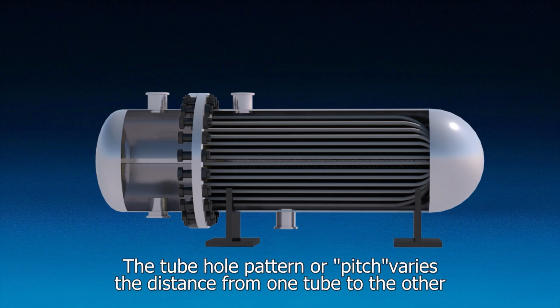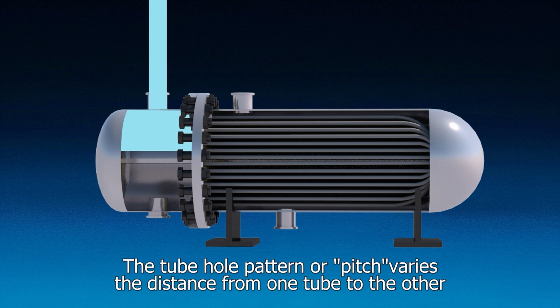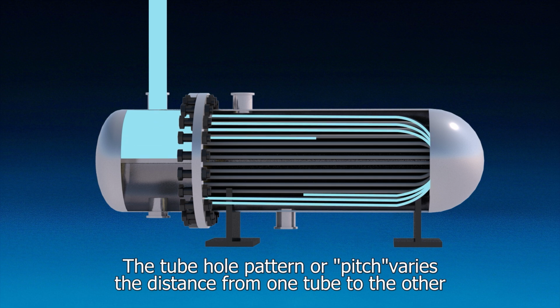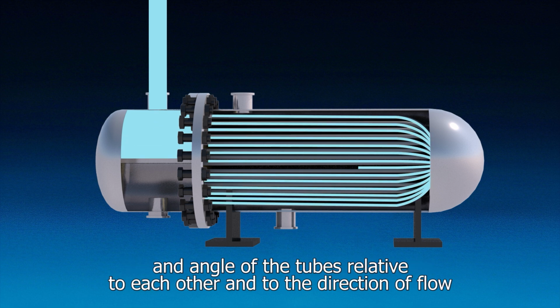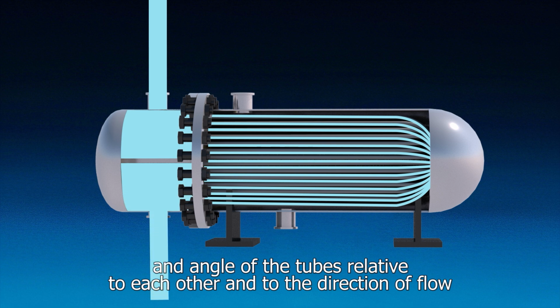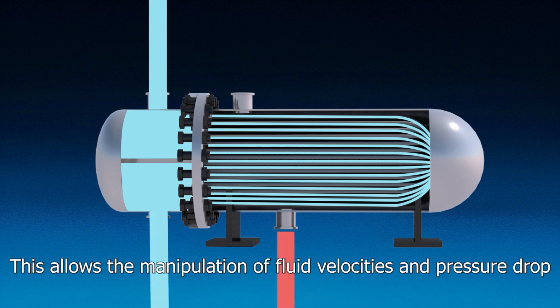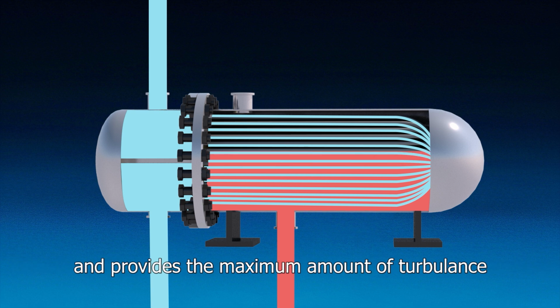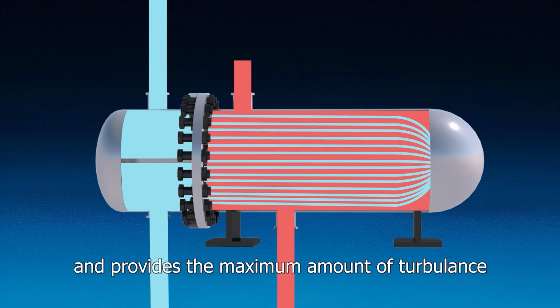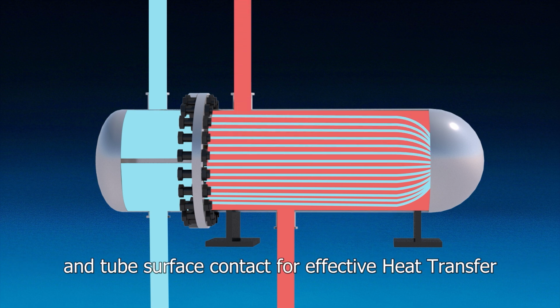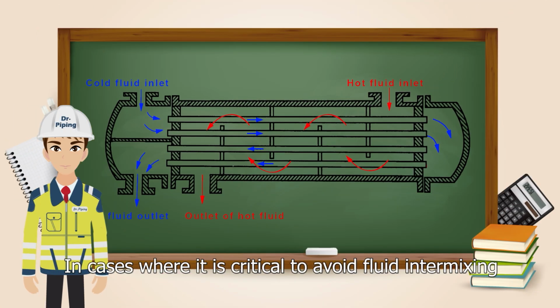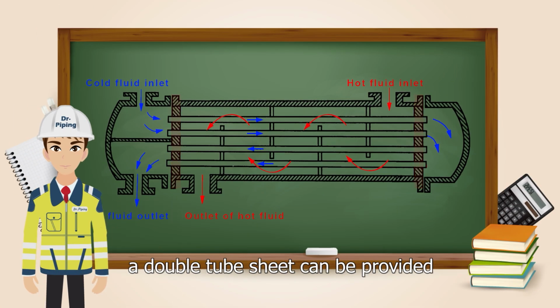seal. The tube hole pattern or pitch varies the distance from one tube to the other and angle of the tubes relative to each other and to the direction of flow. This allows the manipulation of fluid velocities and pressure drop, and provides the maximum amount of turbulence and tube surface contact for effective heat transfer. In cases where it is critical to avoid fluid intermixing, a double tube sheet can be provided.